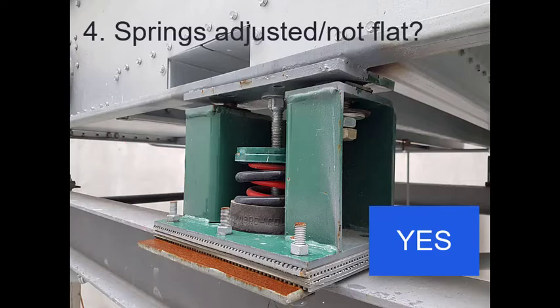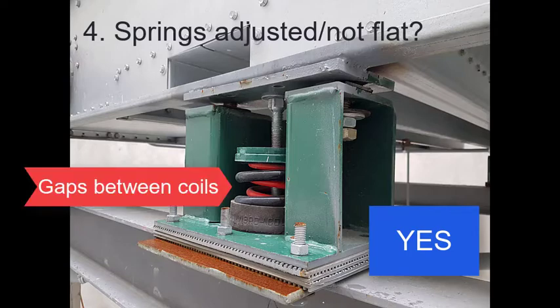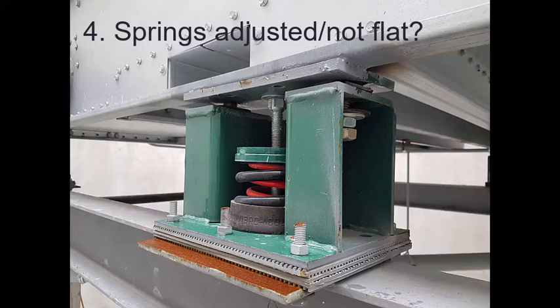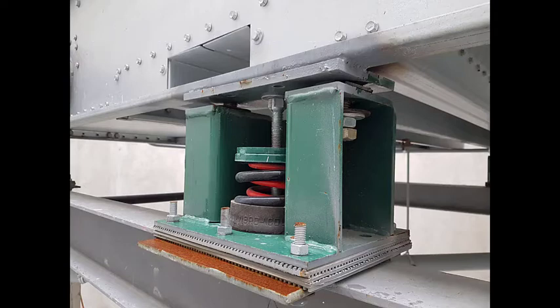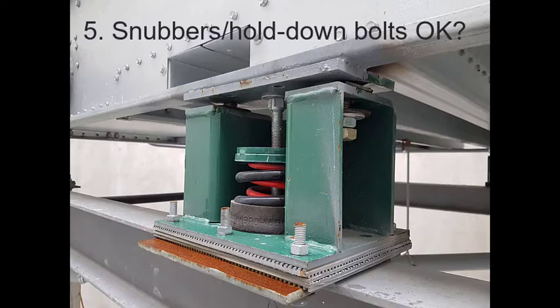It is also important to note that the springs are not flat or fully compressed. If the spring coils were touching each other, that would mean that there was too much weight placed on the isolator. The spring at location 1 was the most compressed, but still working. Overcompressed springs can often be fixed by readjusting the isolators around the equipment or replacing the overcompressed springs with stronger ones. Are the snubbers in place and are hold-down bolts properly set?